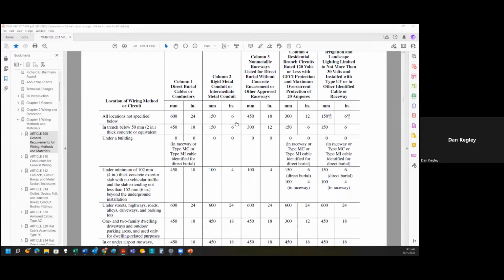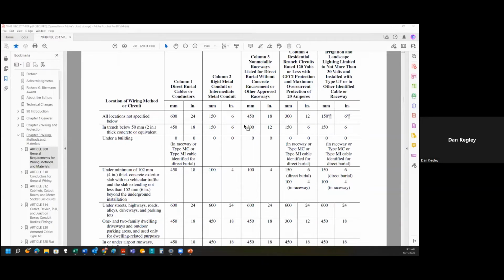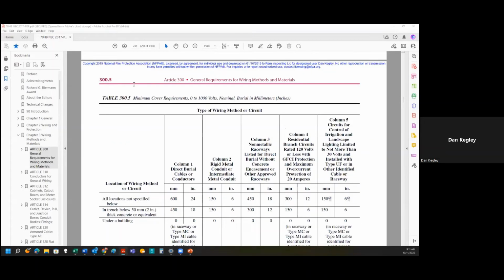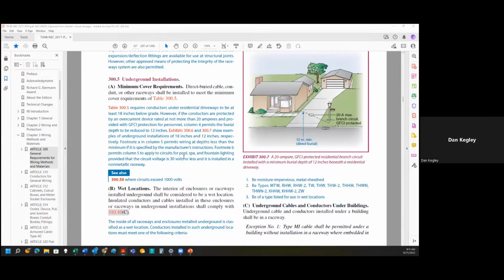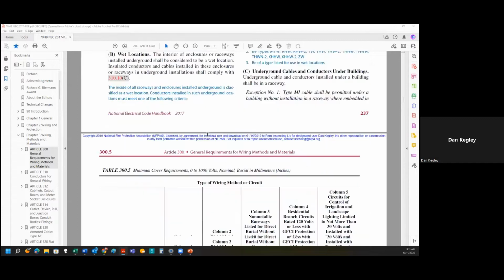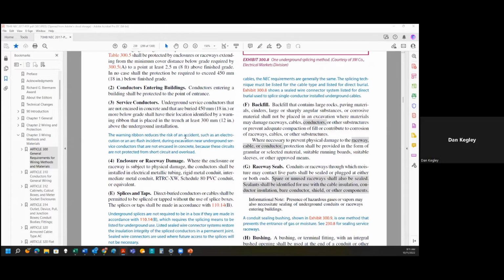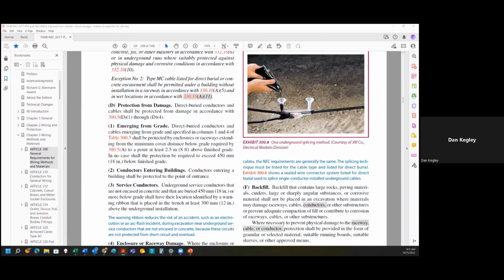So if we go to 300, and then if we go to 300.5, which is where you're going to find all your underground installations, we just looked at the minimum cover requirement in 300.5(A). It goes into wet locations, underground cables and conductors under buildings. So there's quite a bit here. And then if we follow through, D is protection from damage. E is splices and taps, and direct buried conductors can be done, backfilling.